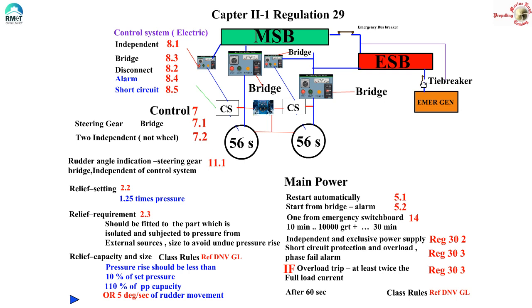When the main source is restored, this tie breaker will disconnect the emergency supply. How long should this emergency source supply the steering gear? Regulation 29.14 says it should be 10 minutes, and if you are a ship of more than 10,000 GRT then it should be 30 minutes. That means the emergency generator or emergency source should have enough fuel or capacity to continuously give uninterrupted power for 30 minutes till you are able to restore the main supply.